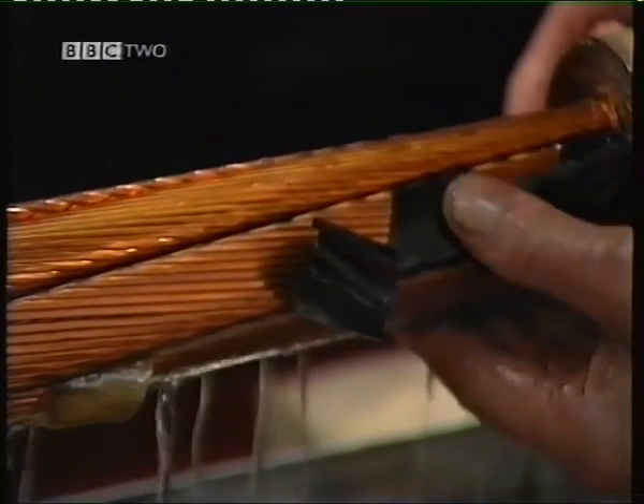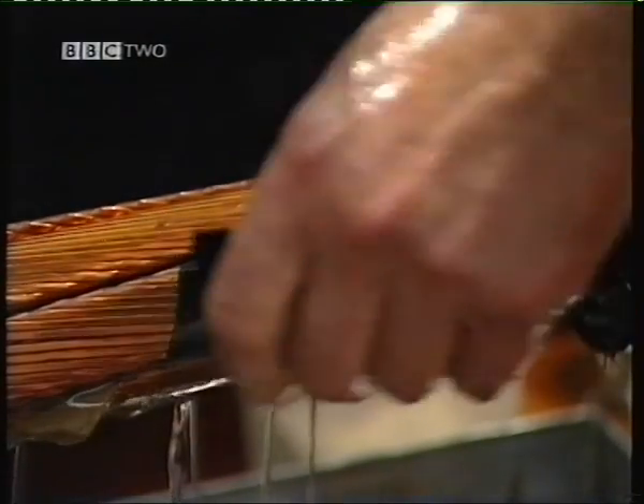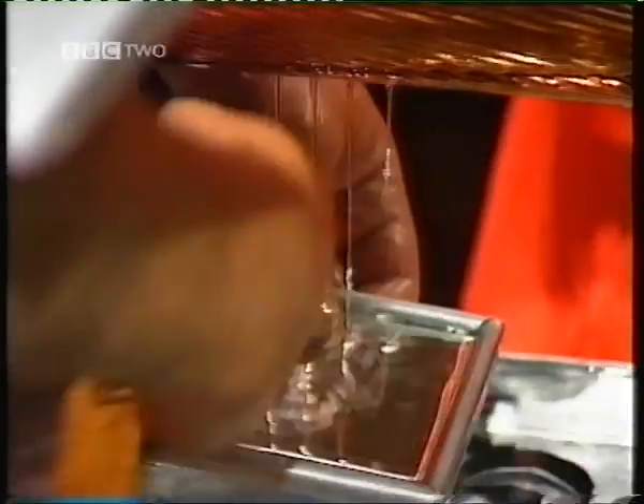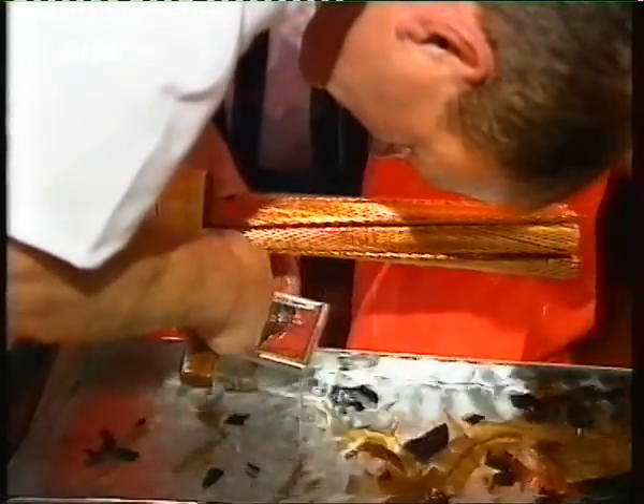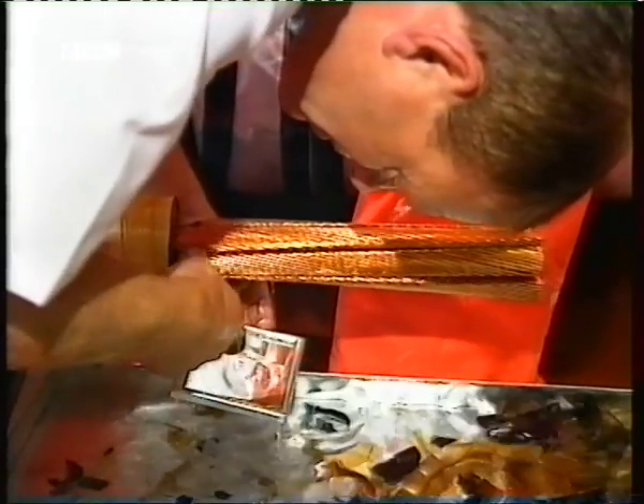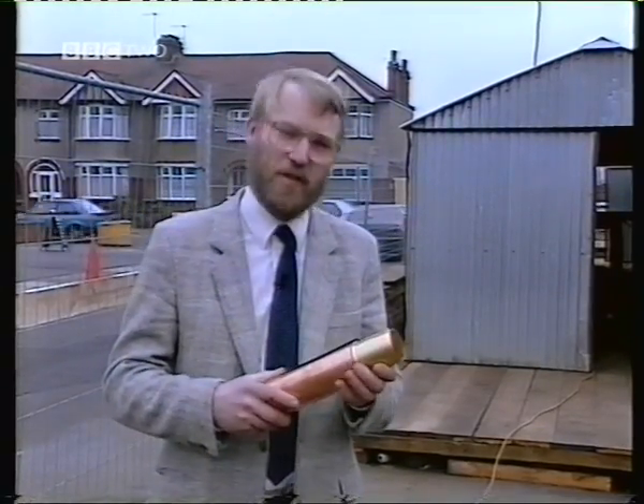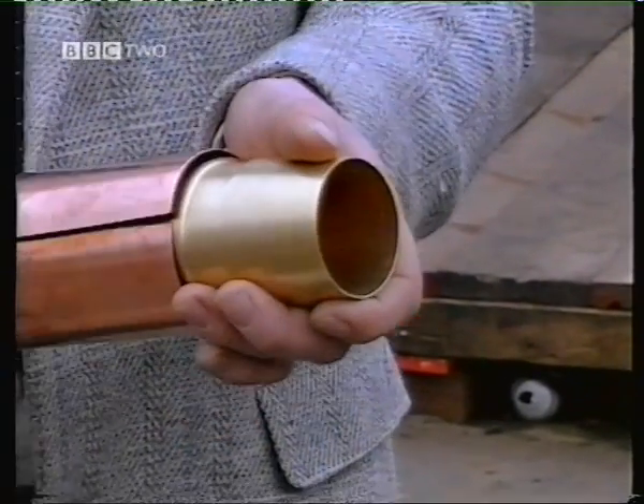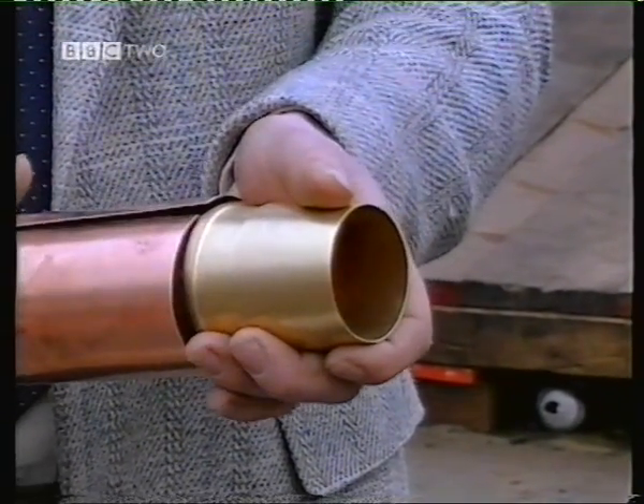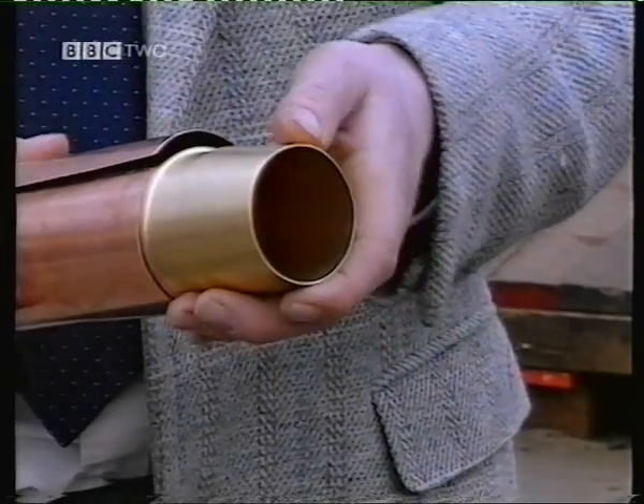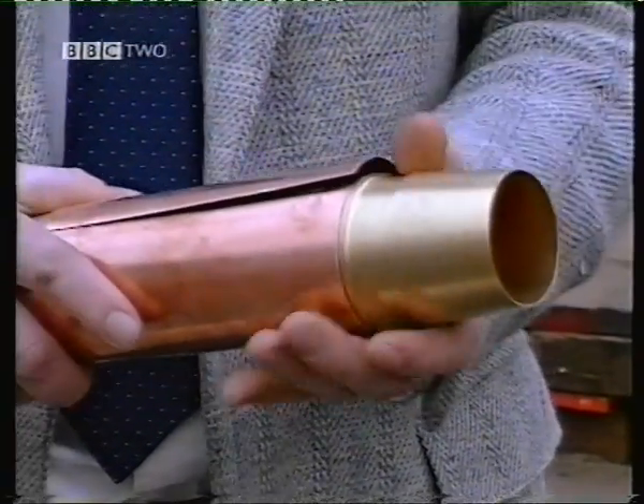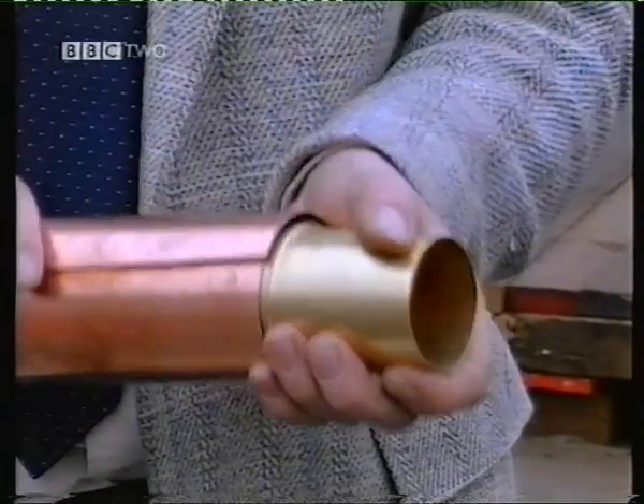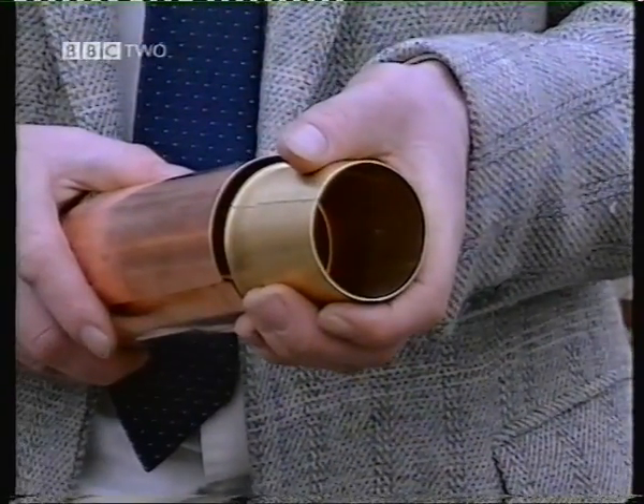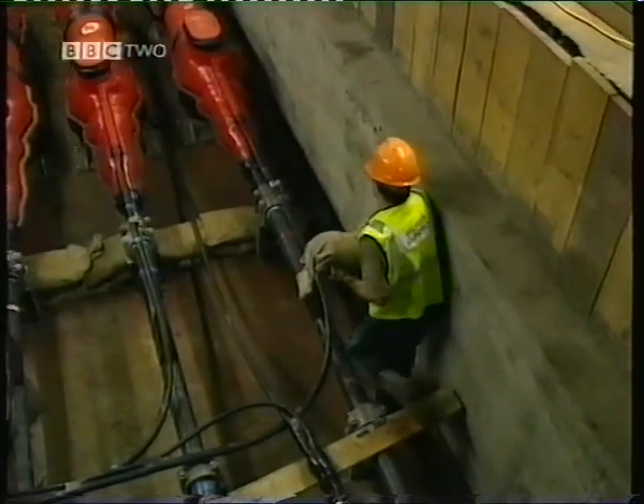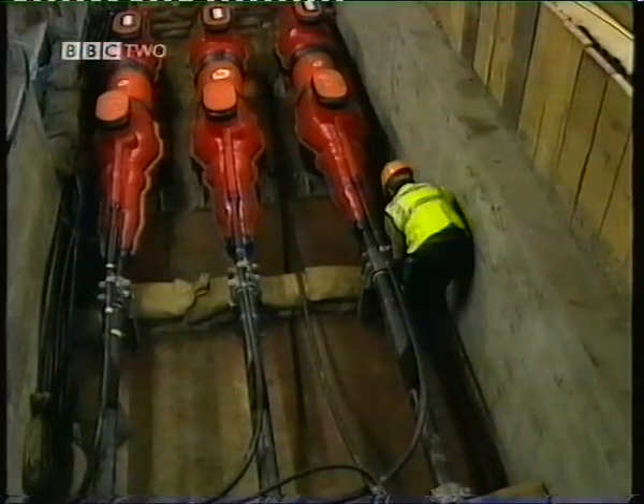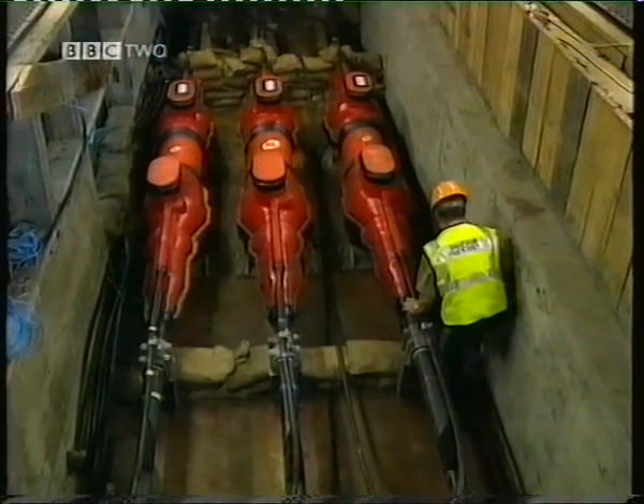The centre conductors are copper. Here they're being scrupulously cleaned, with all paper debris being removed prior to making the electrical joint. This is the ferrule, the piece that actually does the electrical connection. It's what you might expect. It's brass and copper, brass end caps on a main copper body here. And you put a conductor in from this end and the conductor in from that end, and then crimp the ends tight. After some 18 hours hard work, the electrical connections and the hydraulic seals are complete and encased underground.